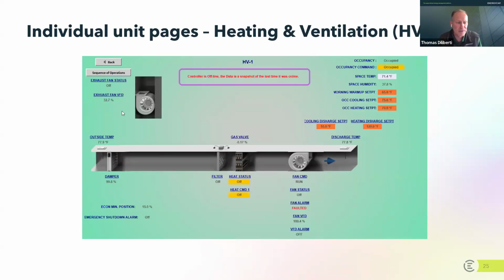This one here is an example of a screen where things start to light up different colors because the controller's offline. So as you're scrubbing your system and looking for opportunities, try to find these things and bring attention to this, because it's one of two things. It's probably running all the time, or the other possibility is many times these controllers, if they go offline, will run the last schedule that was programmed into it. Again, that's a decision that somebody had to make. So you want to find out what's going to happen if your controllers go offline, but look for these in the system. Most building automation systems will flag this in a way similar to what's seen here.